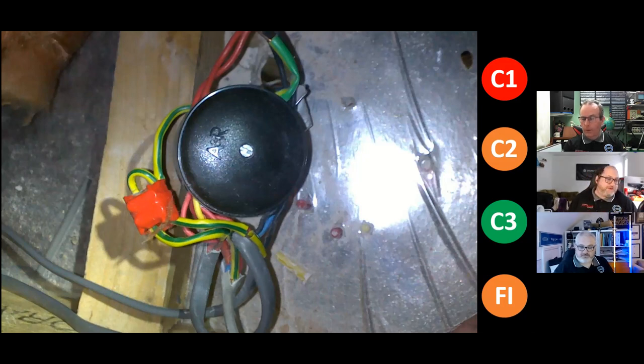So if you've observed that this has thermal insulation on top of it, do you just remove the thermal insulation and then potentially impact the house's energy performance categories? Or do you then go, oh, I'll have to FI this and then actually calculate the impact of that thermal insulation if that value of derating is not there for you in the calculations? I have found when I've had to crawl through lofts doing these, I will always uncover the electrical connections from the insulation, and I would rather leave it there and allow the heat to dissipate. And I will just tell the customer that I've left the insulation exposed with the C2 recommendations.